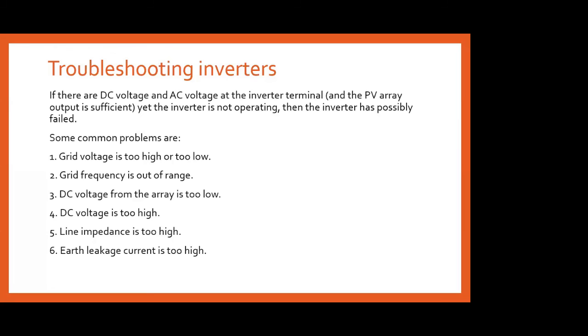Then the last one is earth leakage current is too high. What do we mean by that? If the earth leakage current is too high, this case will arise only for the transformerless inverters. Okay, this problem will not be there for your transformer inverter. It is only for the transformerless type of inverters. So we have to take care of the earth leakage currents also.